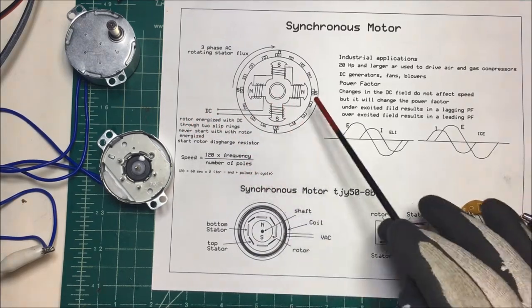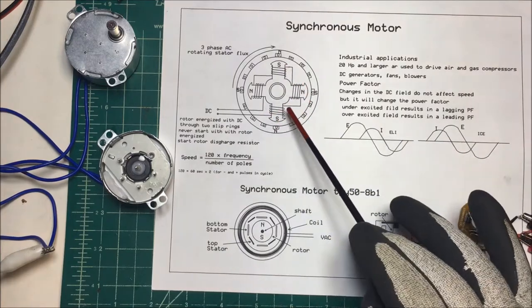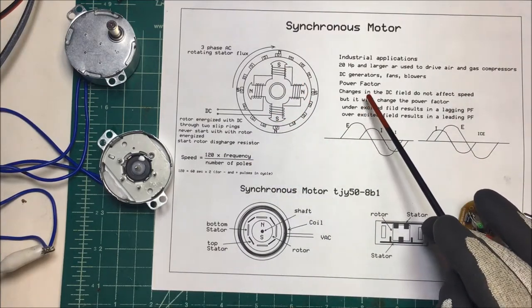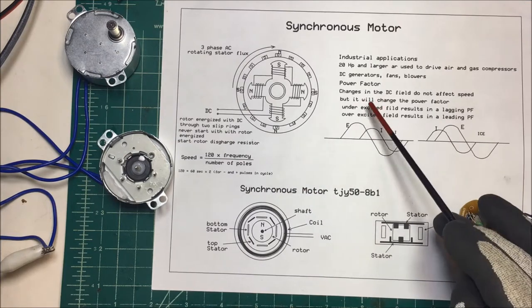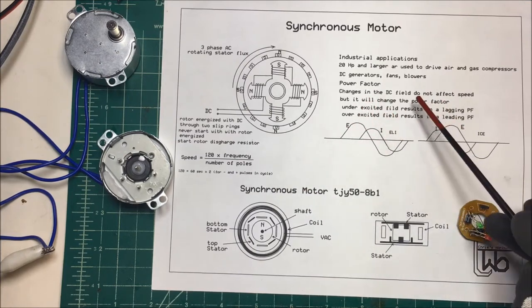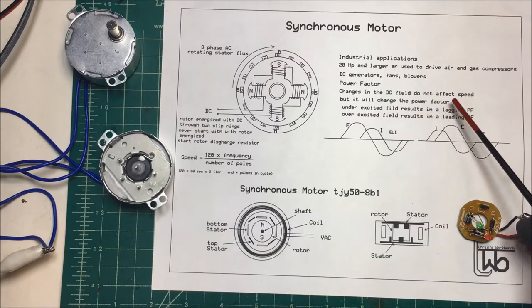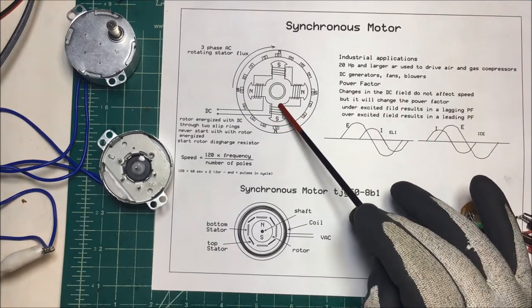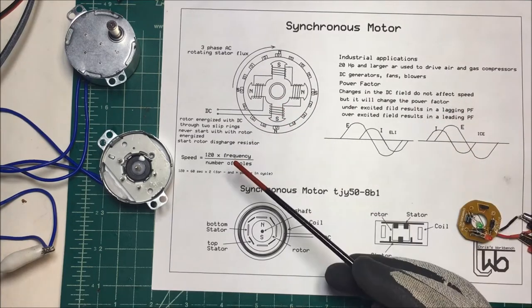The reason they use these in industrial applications is that they can correct the power factor. Most of the time they use them for air handling equipment because it just stays on all day long. If you change this magnetic field here, it doesn't affect the speed but it changes the power factor.